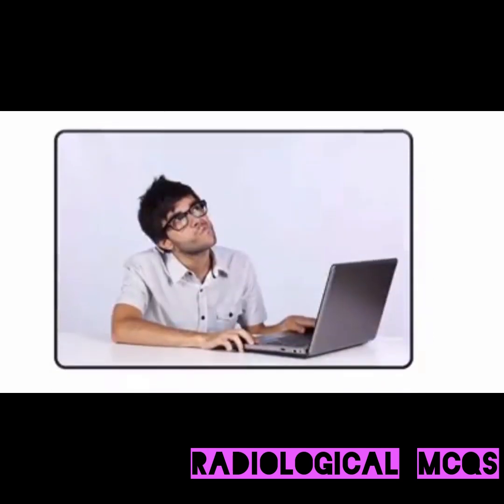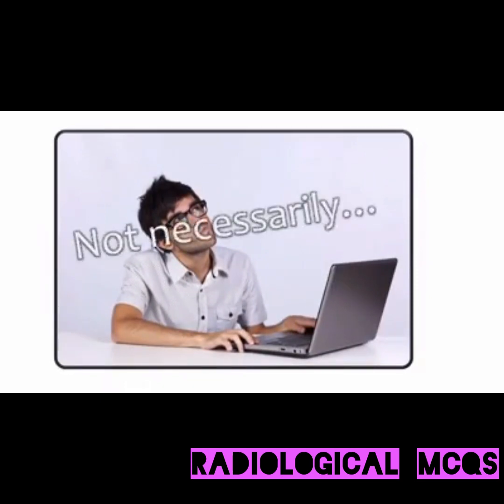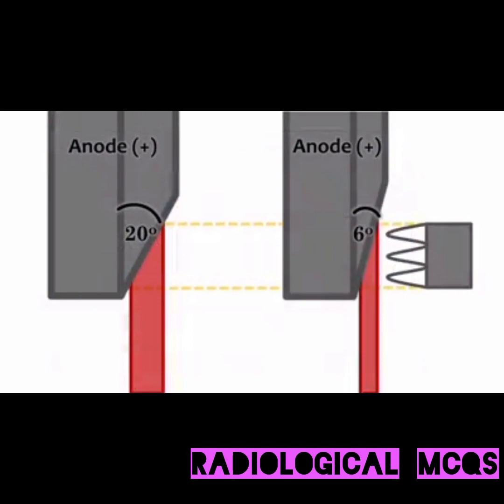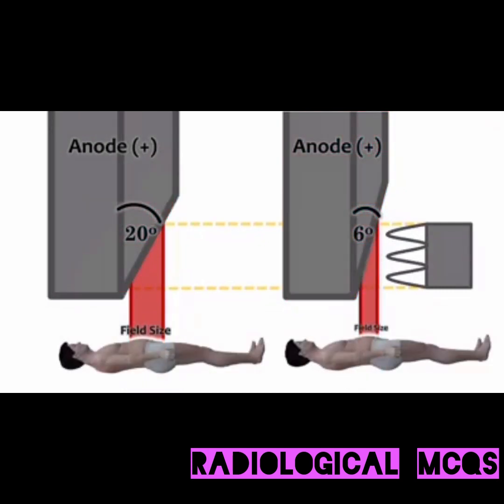So would it make sense to just produce all X-ray equipment with small anode angles? Not necessarily. One major drawback to utilizing small anode angles is that as anode angle size decreases, that is, gets smaller, the ability of the anode to tolerate high exposure outputs also decreases. Another drawback to utilizing small anode angles is that as anode angle size decreases, image field size also decreases.